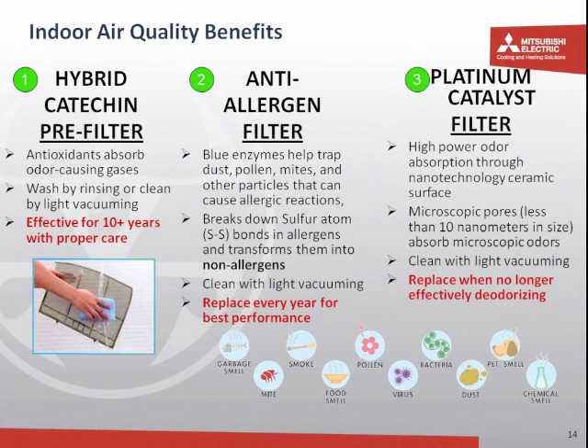The other benefit is that these filtration systems are there located in the space. They're inside that indoor unit. Simple hinge open, the filters can be removed. Two of those are cleanable with either light vacuuming or rinsing. The third is replaced every year. In all cases, they're easily accessible to keep the maintenance current, and the replacements are easily available through our distribution network throughout the country.